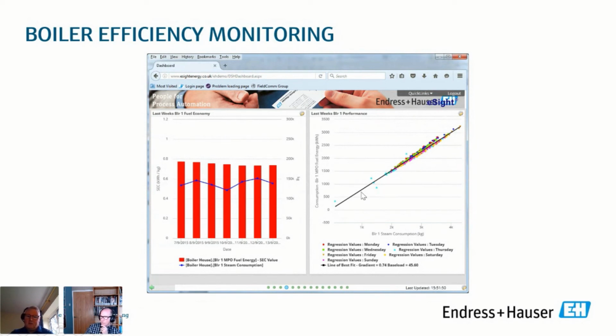Now they form a straight line, and the line of best fit here is just the average efficiency of that boiler. It's not to say it's good or bad—this is the average of the current operation, and you can see sometimes we've been above this line and sometimes below. So for a given steam demand, say 3 tons here, sometimes we've had more fuel to raise that steam than other times.